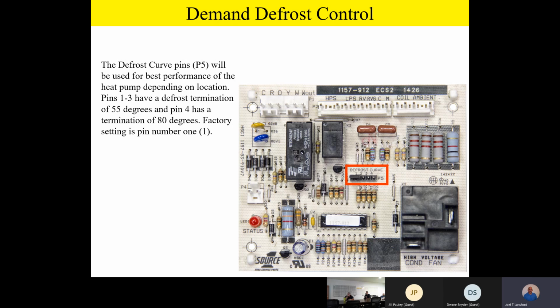But on a 2-ton, if it's 20 degrees outside again, the optimal coil temperature for defrosting and making sure the coil's clear might be 17 degrees. So it's not a linear line, it's a curve. Based on the tonnage, the SEER rating, the compressor efficiency, and all that engineering mojo, there's going to be an optimal place on that coil and ambient temperature curve to defrost that unit. So the reason we give you different pin selections is because, based on the tonnage of the unit, you're going to get best performance and optimal defrost efficiency by having it on the proper pin setting. That's why they do that.